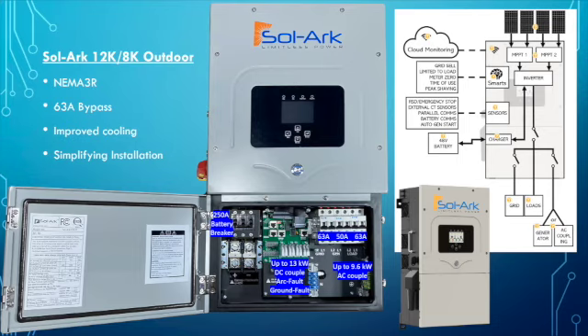In addition, if there is a problem with the system, let's say there's some particular alarm, like a GFCI detection on the MPPT strings, the inverter will shut down as required by law, but we will bypass the grid over to the loads so that the loads stay powered, and it requires a power cycle to resolve. So likewise, if there's some failure in the inverter, there is a bypass as well so that the grid automatically connects to the loads to keep it powered if it can, if the computers are still operational.